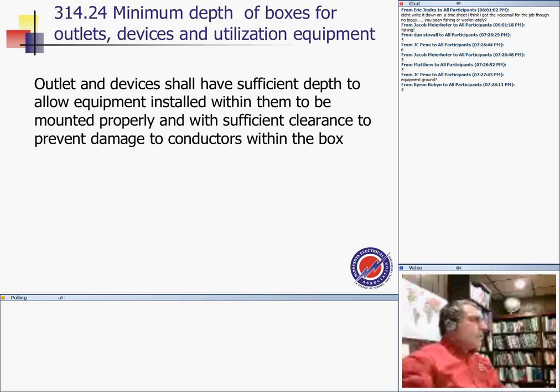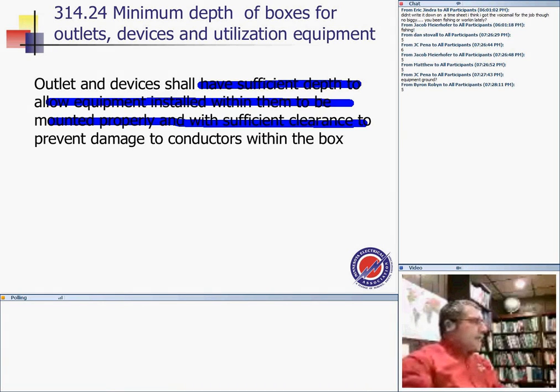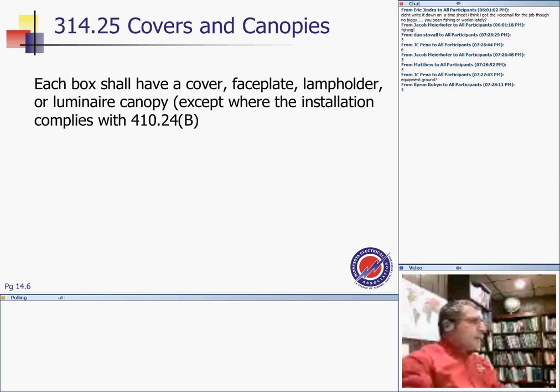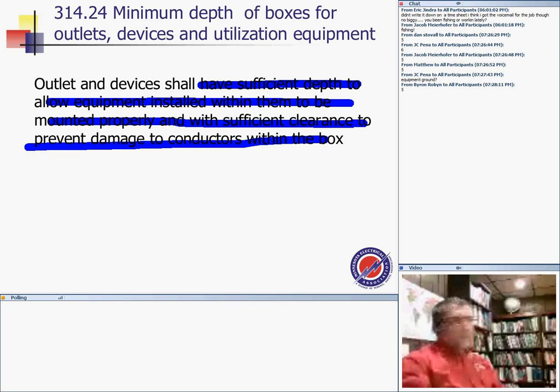Depth of boxes and outlets, guys. Boxes shall have sufficient depth to allow equipment installed within them to be mounted properly and with sufficient clearance to prevent damage to the conductors within the box. In 2008, they changed it, guys.